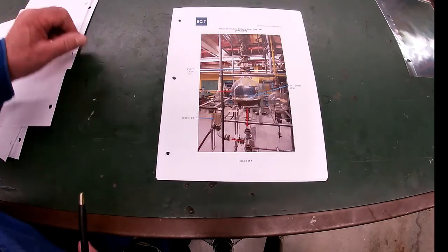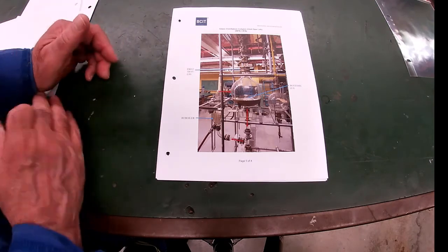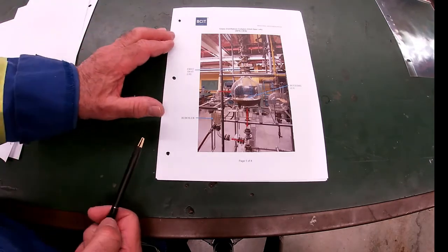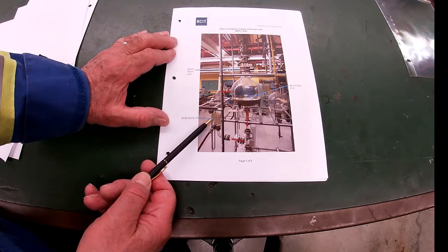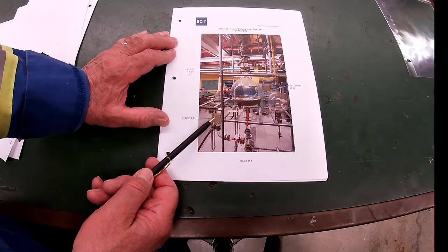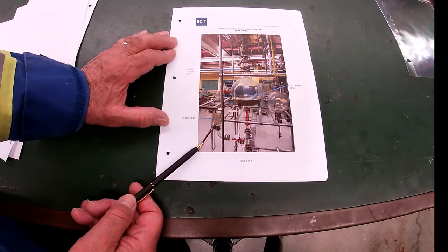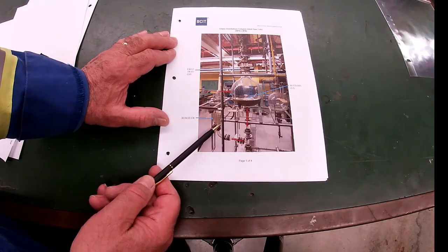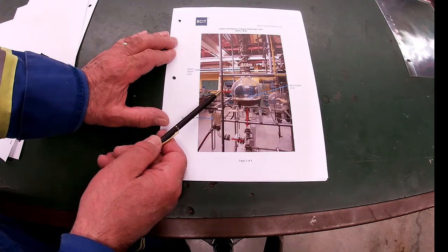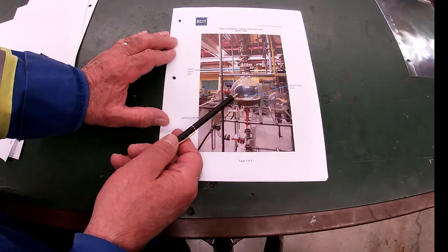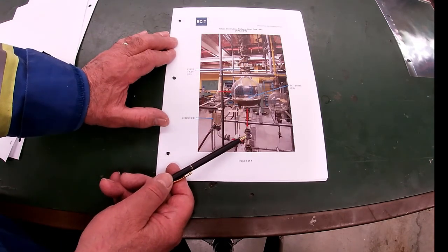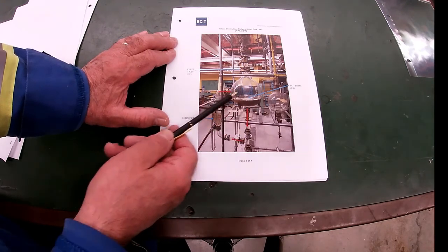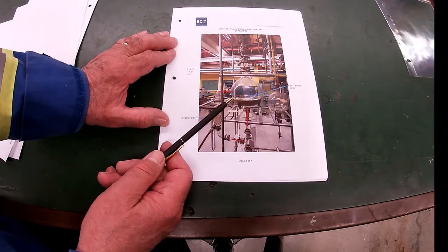Okay, then this is just some quick pictures of the column so that when we do see things happening on the video, you'll have a better perspective of what's going on. As we heat it up, when we apply steam into this reboiler, there's a red hose in here, and you'll see on the video the steam going around inside the tubes and coming out as condensate. When we heat it up, it expands in volume, and as a result fills up and spills over into the actual bottom section of the distillation column. The product then is drawn out and circulates around and eventually starts to thermal siphon, and this is how we actually heat the liquid up.